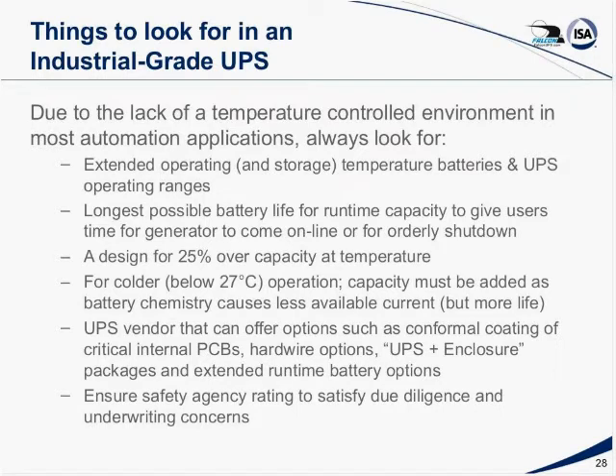With the online UPS, because it's a seamless transfer to battery, number one, the battery just takes over as the energy source, and you have such a wide input range, and frequency is not an issue, because you're regenerating the sine wave. Generators are typically not a problem.